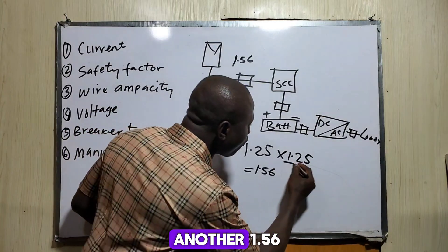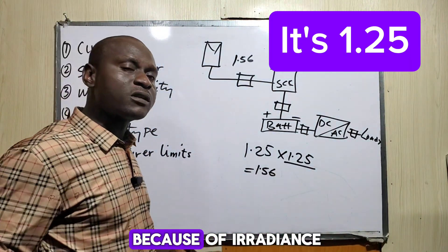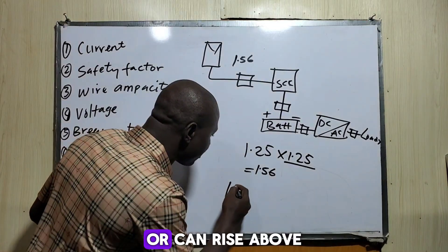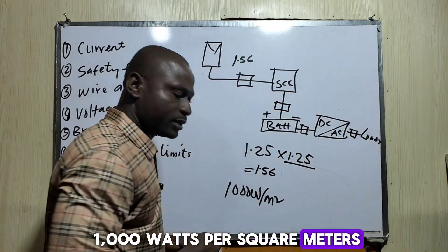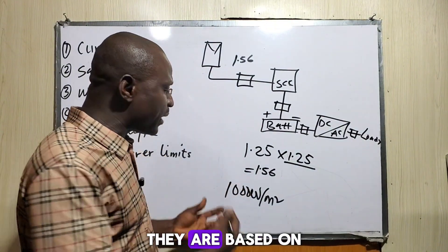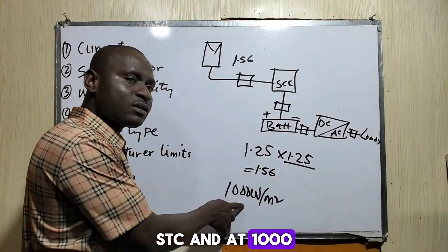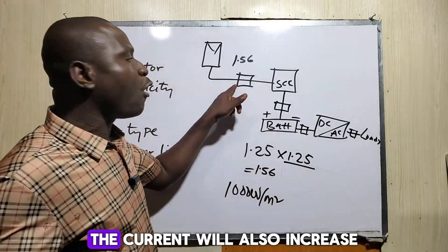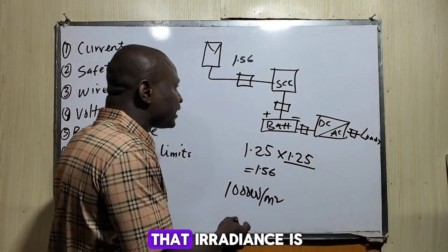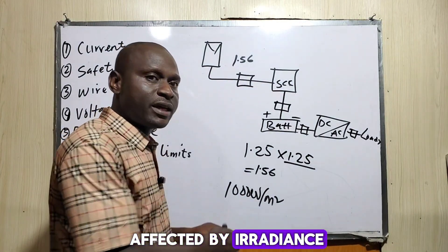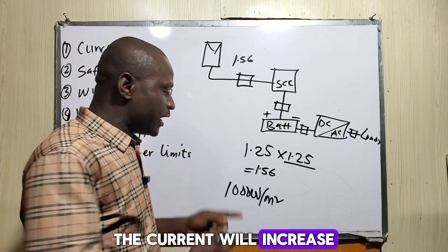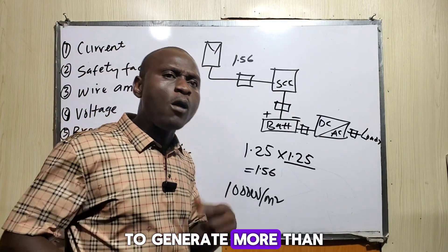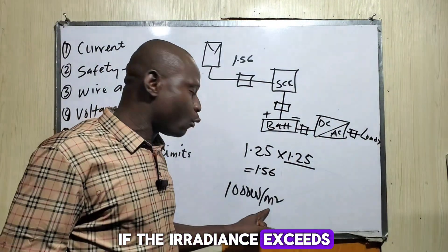We use 1.56 because of irradiance. During the day, the irradiance can rise above 1,000 watts per square meter. The solar panel data is based on standard test conditions (STC) at 1,000 W/m². If the irradiance increases above 1,000 watts per square meter, the current will also increase. Solar panels have the tendency to generate more than their rated capacity if the irradiance exceeds 1,000 watts.